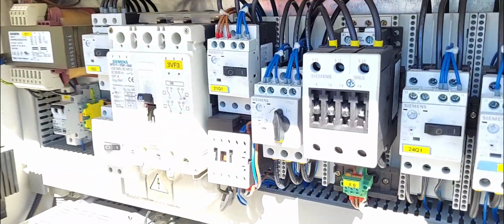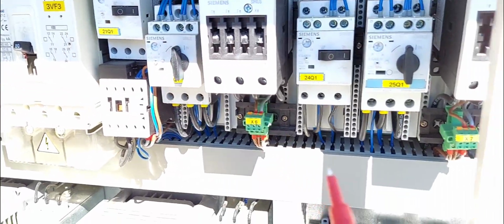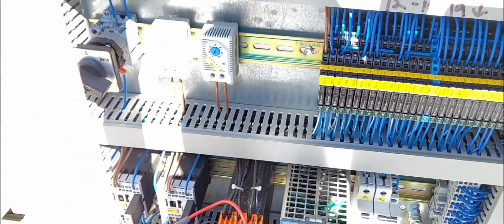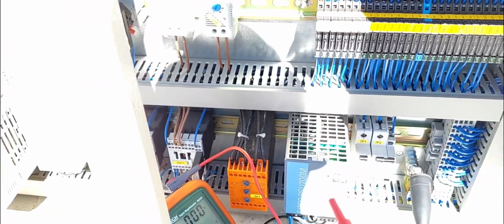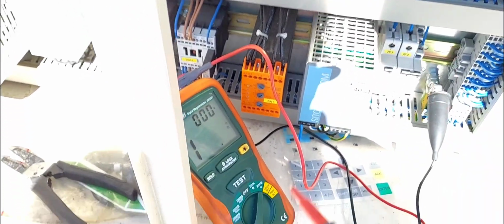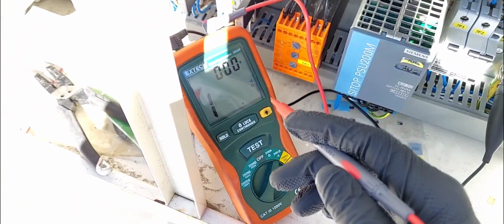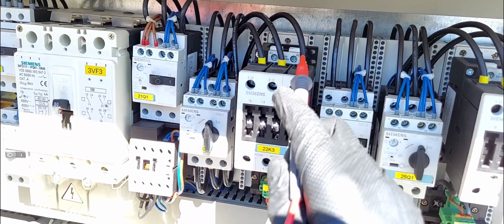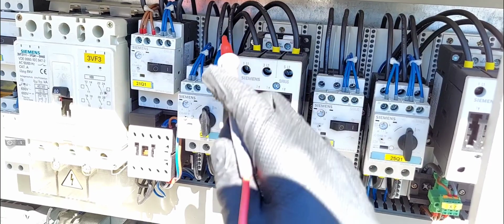At that point, with vibration, when the compressor works hard and it's really hot, it will trip your breakers, trip your overload, blow your fuse, and then you replace these things and put them back together. It will work for a while. A couple of weeks later, same problem. You've got to run a Meg test, check the windings, or check the wires that leave the contactor and go to the compressor.